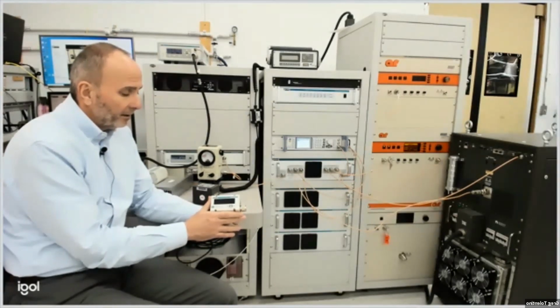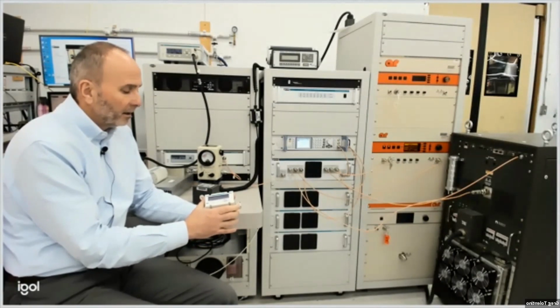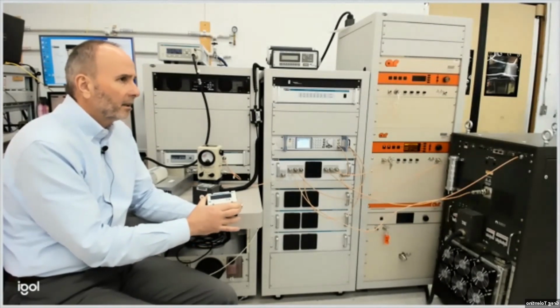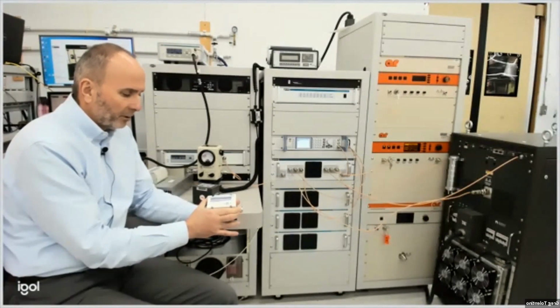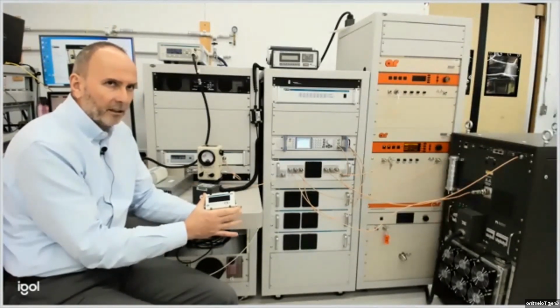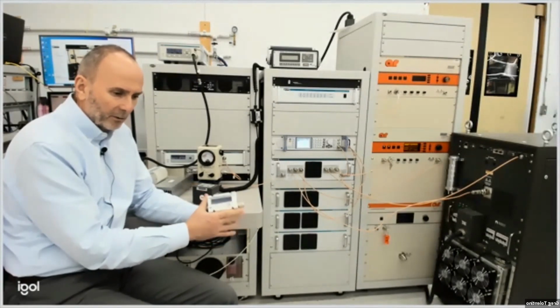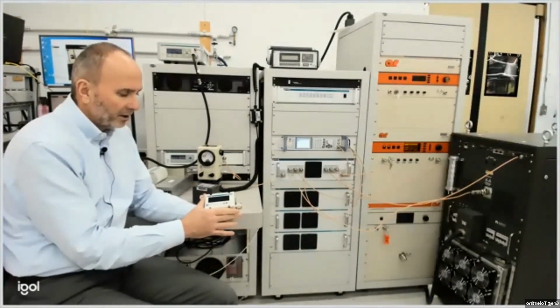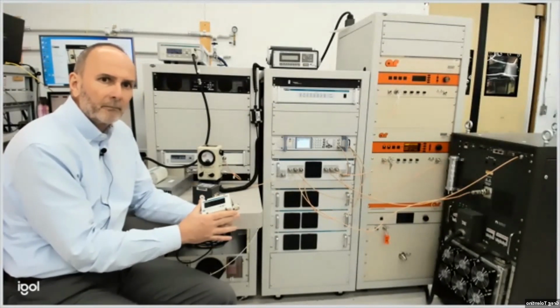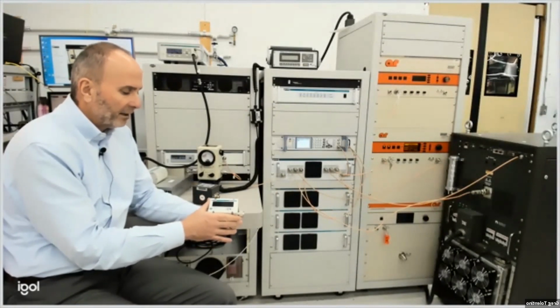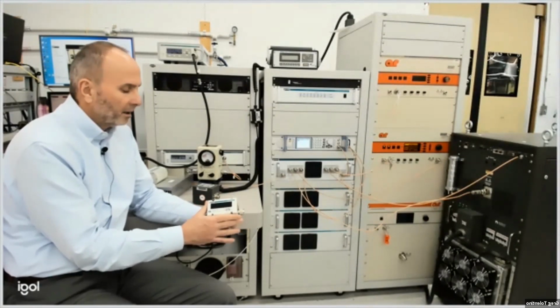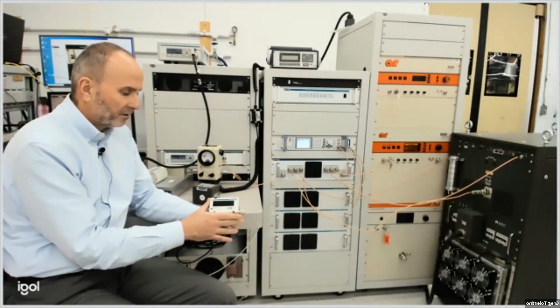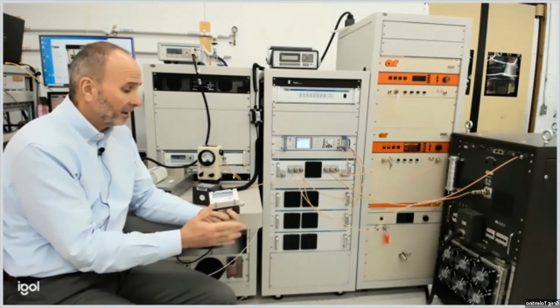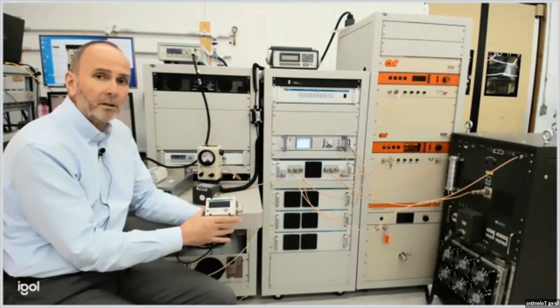And then their accuracy at a calibrated point is always better than 1%, closer to 0.5%, I think. And then accuracy between points really depends on the calibration that was ordered. If calibration frequencies and powers are far apart, maybe we get outside 1% between points. If the calibration table is fully populated with an extensive test, then better than 1% across the board.